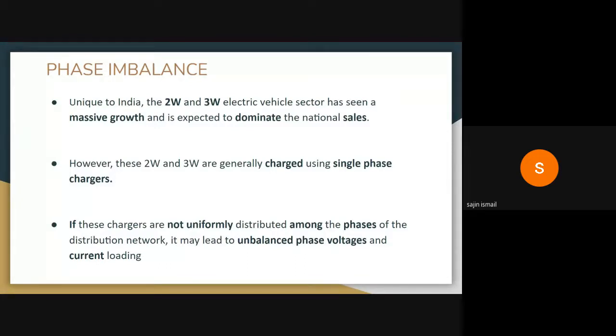When you use a single phase charger in a distribution system, we have three phases from a distribution transformer. If most of the chargers are distributed among one particular phase, or not evenly distributed, the demand at one particular phase will be very high - 3.3 kW into 10 houses becomes 33 kW demand there, while in other phases it will not be there. So it will create a huge imbalance.